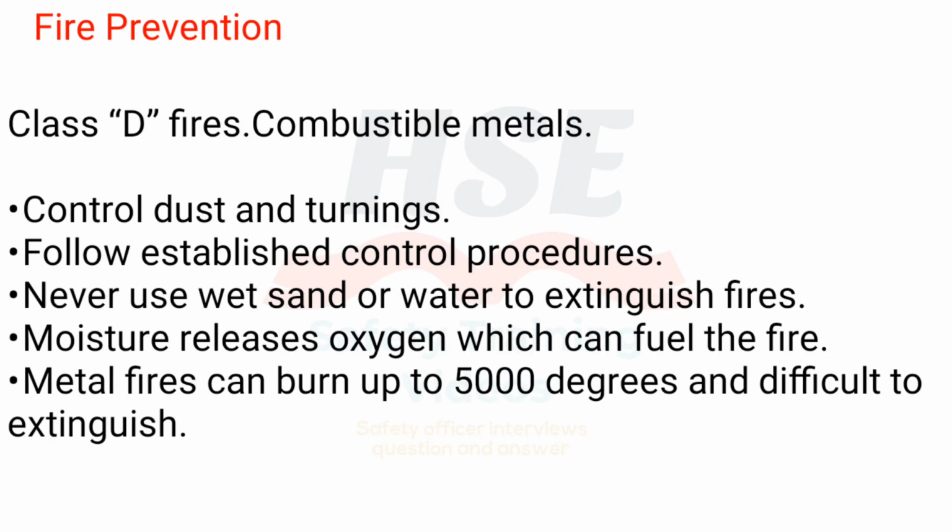Class D fires: combustible metals. Control dust and turnings. Follow established control procedures. Never use wet sand or water to extinguish fires. Moisture releases oxygen which can fuel the fire. Metal fires can burn up to 5,000 degrees and are difficult to extinguish.